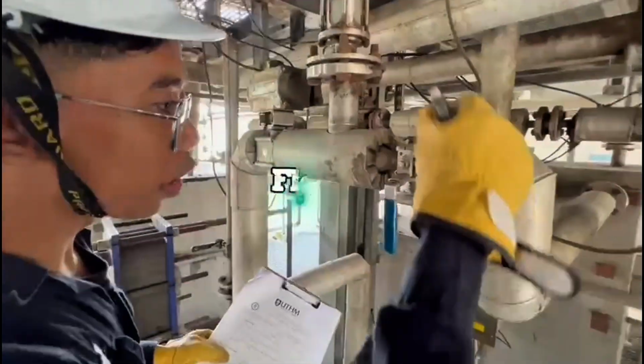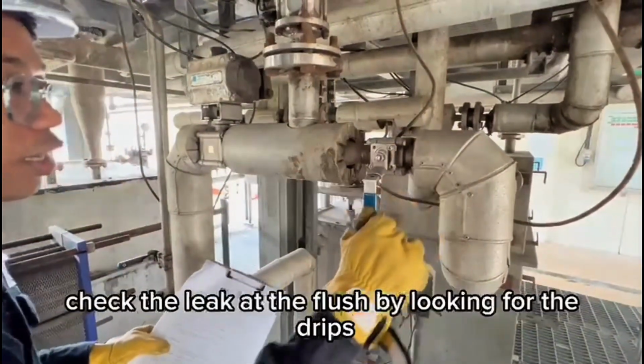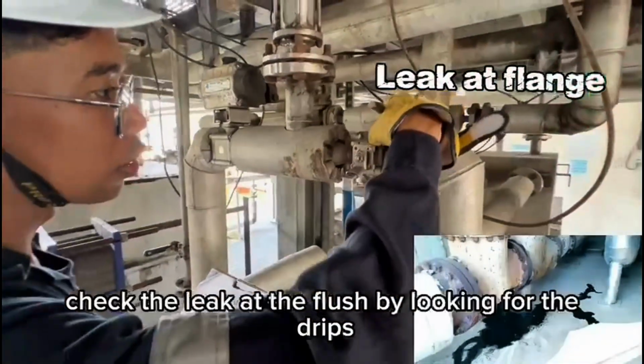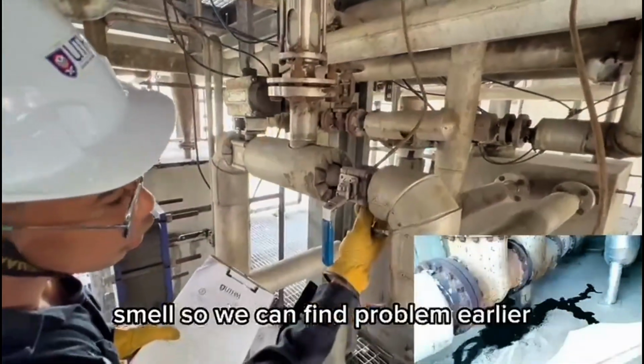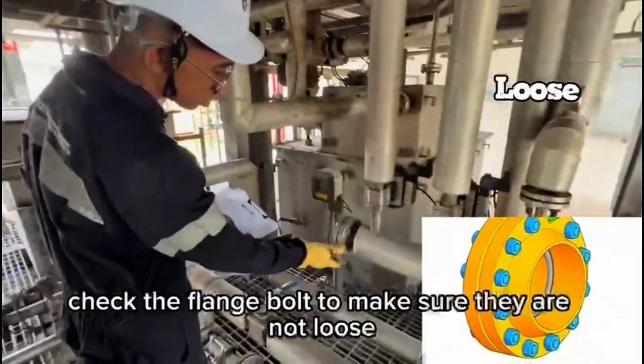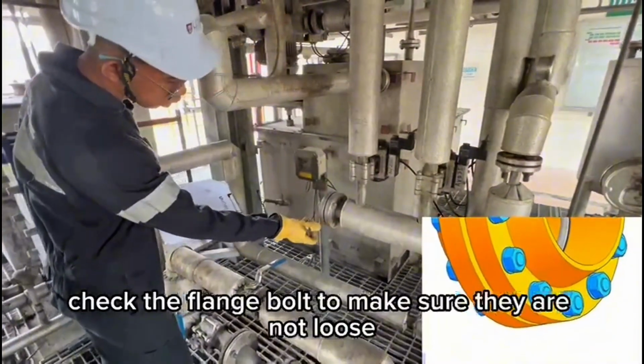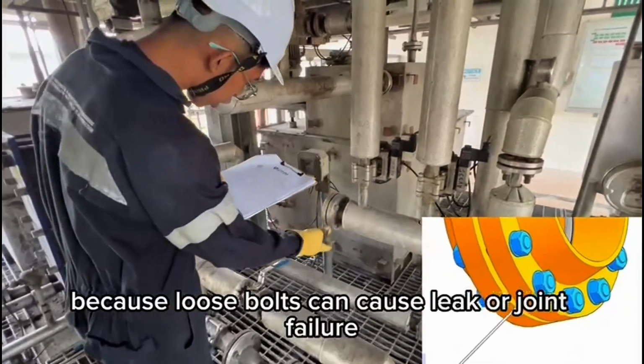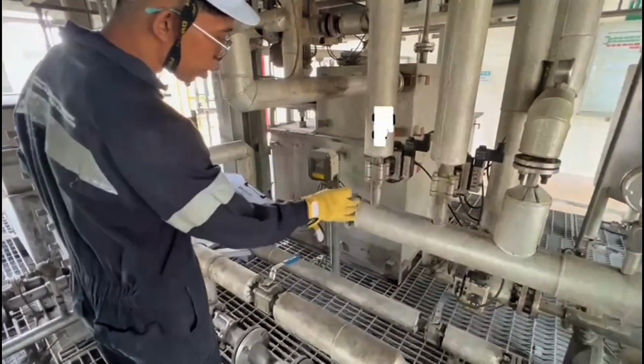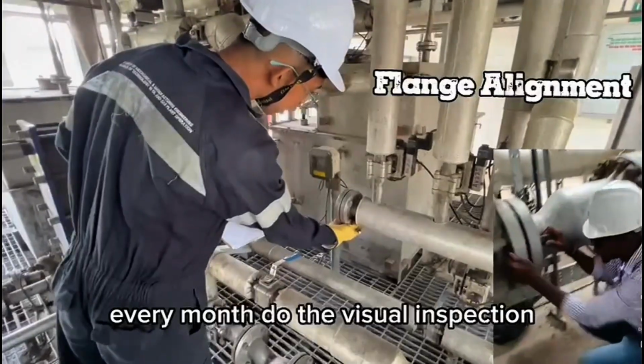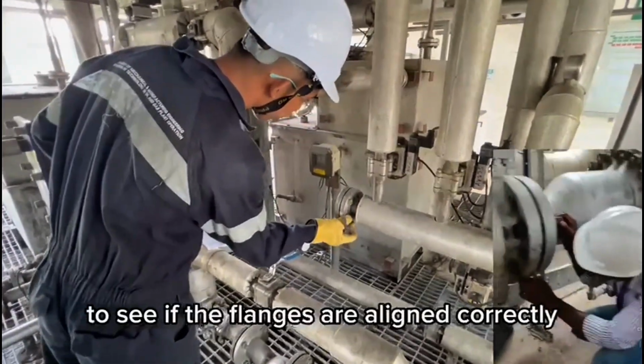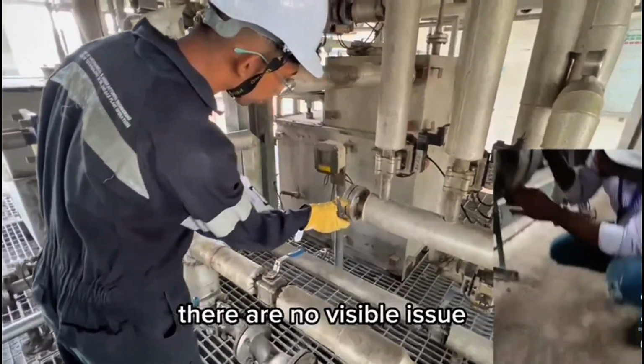Every day, check for leaks at the flange by looking for drips and smell, so we can find problems earlier. Once a week, check the flange bolts to make sure they are not loose, because loose bolts can cause leaks or joint failure. Every month, do a visual inspection to see if the flanges are aligned correctly and there are no visible issues.